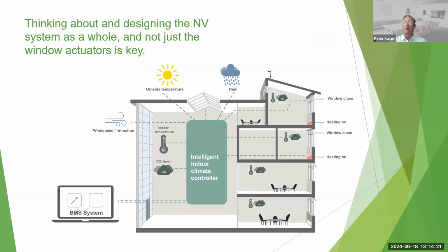So thinking about designing the natural ventilation system as a whole is very important, and not just the windows themselves. There's a bunch of different aspects that synchronize or work together to make the system work efficiently as a whole. These include outside temperature and rain sensing, wind speed and direction sensing, heating system feedback and communication with the window natural ventilation control system, and then a link to the building management system, if there is one, which enables a highly configurable design for the overall system so that it optimizes the efficiency and effects of the system.